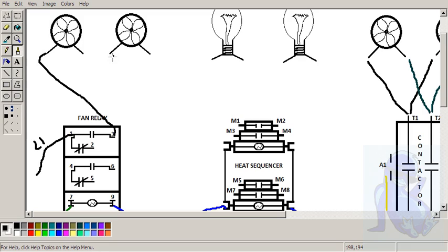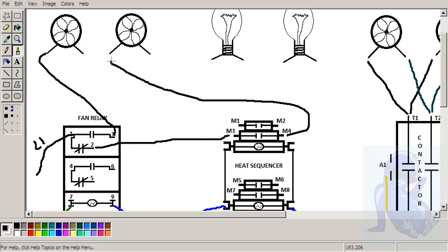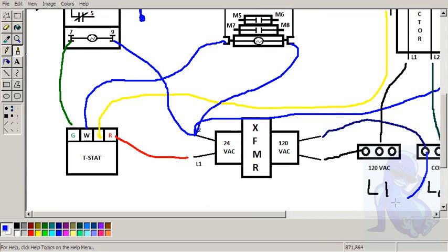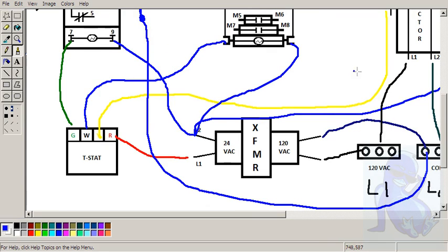and your low-speed fan does not go directly to 2, because remember, this stays energized. You're going to run 2 to your heat sequencer, and the power is going to stop right there until it's called for. When low heat is called for, this will allow power to pass through, and you can run that power to your low-speed fan. You're also going to want that to go back to L2. Remember, L1 to switch to load back to L2. So we're going to run these back to L2, or common. I'm going to make a little terminal post just to connect them together. And there you go. Now you got L2.